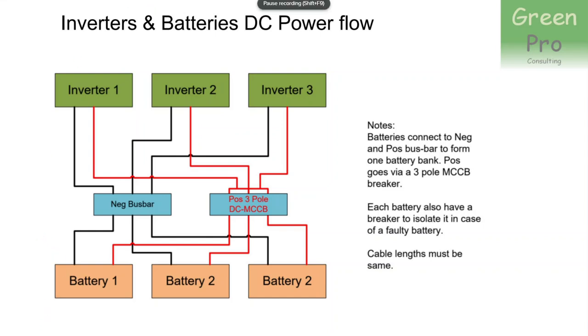Let's look at the DC power flow. You take battery one, battery two, battery three — in this case a three-battery system using three 300 amp-hour Sunsynk batteries, which are just under 16 kilowatt-hours each, giving a total battery bank of between 47 and 48 kilowatt-hours. You connect the negative terminal of each battery to a negative bus bar. I use a small copper bus bar, 30mm by 5mm. I don't switch off the negative — I only switch the positive of the battery bank.